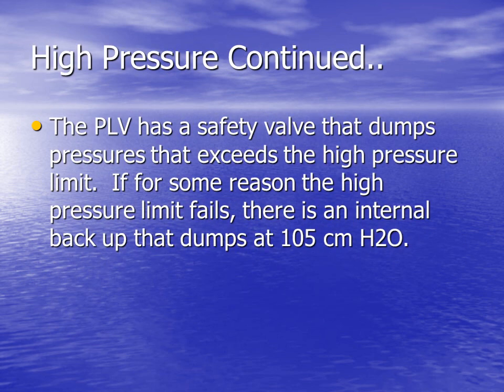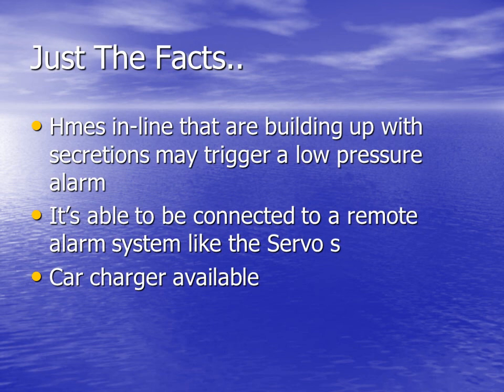This vent has a built-in dump valve to release pressures in excess of the high pressure limit. The backup valve releases at 105 centimeters of water pressure. It's interesting to mention that using a heat-moisture exchanger on this vent may trigger inadvertent low-pressure alarms. This vent has the capability of connecting to remote nurse call alarm systems, and it may also be powered by a car charger of the same type that is used to charge cell phones.